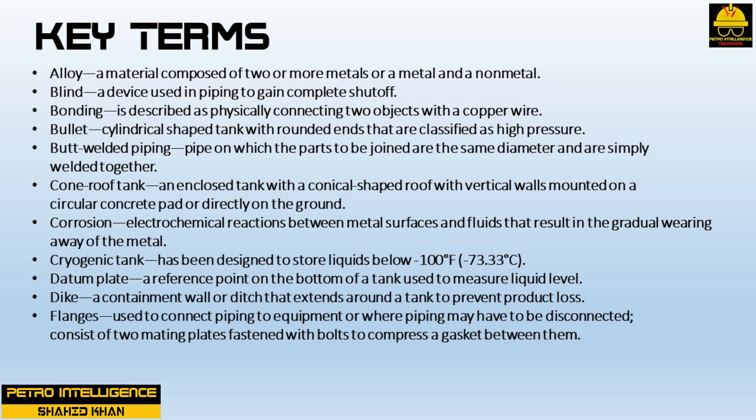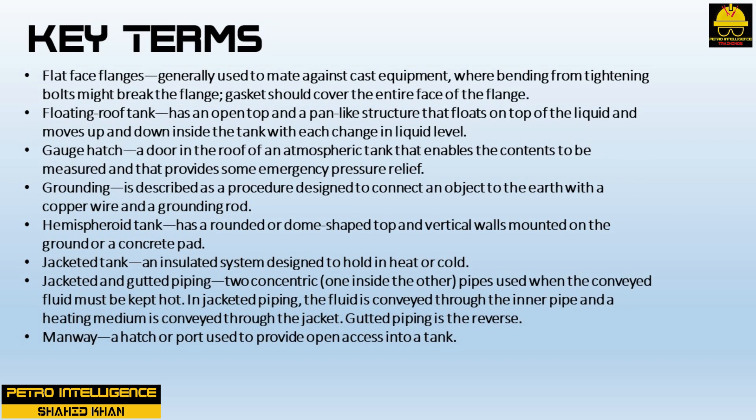A cryogenic tank is designed to store liquids below minus 100 degrees Fahrenheit or minus 73.33 degrees Celsius. A datum plate is a reference point on the bottom of a tank used to measure liquid level. A dike is a containment wall or ditch that extends around a tank to prevent product loss. Flanges are used to connect piping to equipment or where piping may have to be disconnected; they consist of two mating plates fastened with bolts to compress a gasket between them. Flat face flanges are generally used to mate against cast equipment where bending from tightening bolts might break the flange — the gasket should cover the entire face. A floating roof tank has an open top and a pan-like structure that floats on top of the liquid, moving up and down with changes in liquid level.